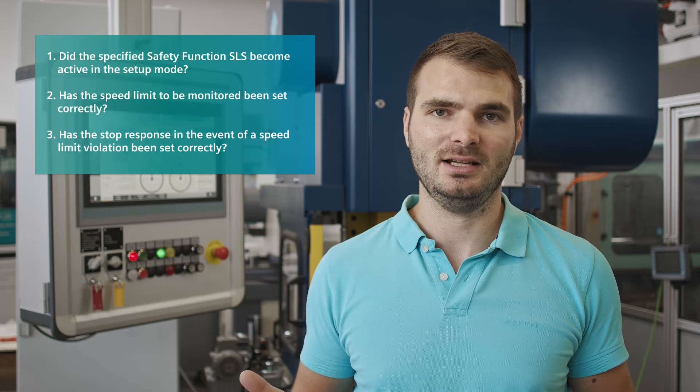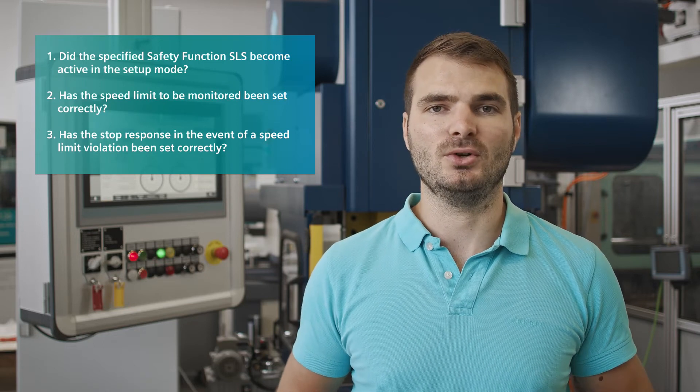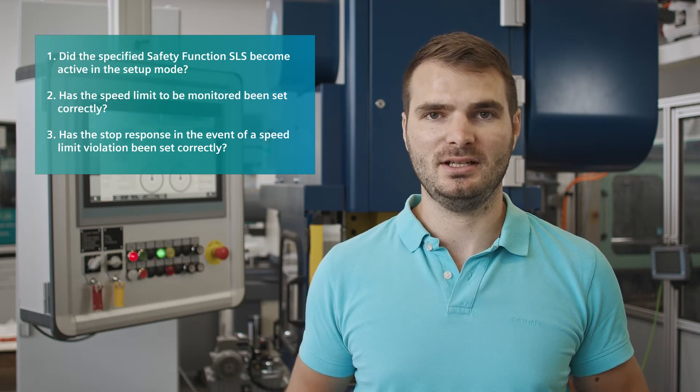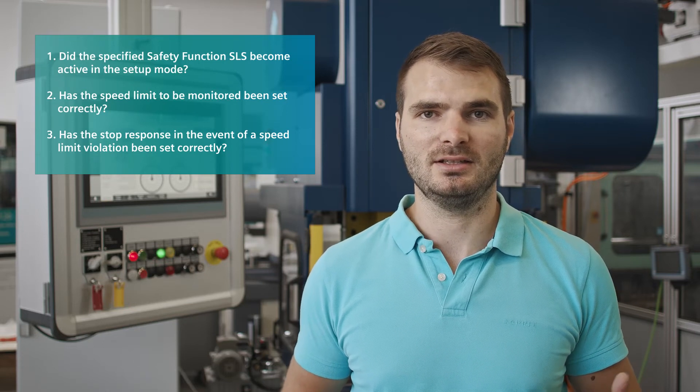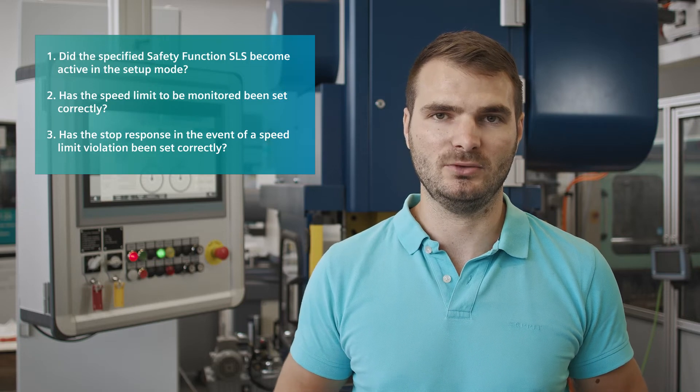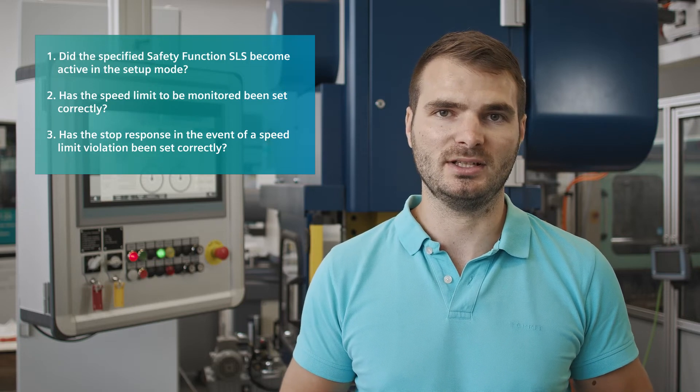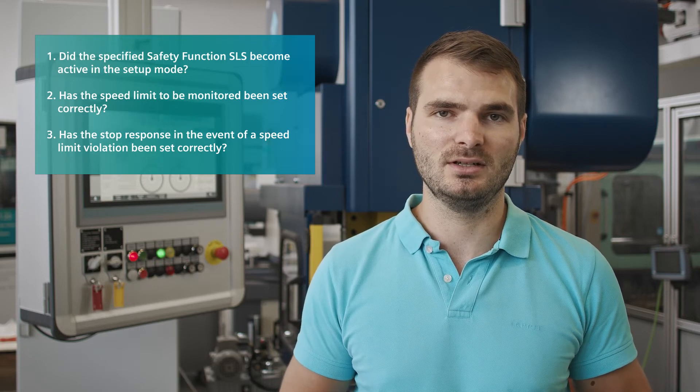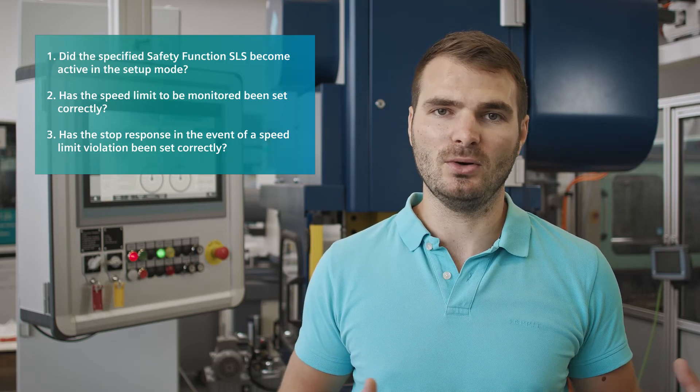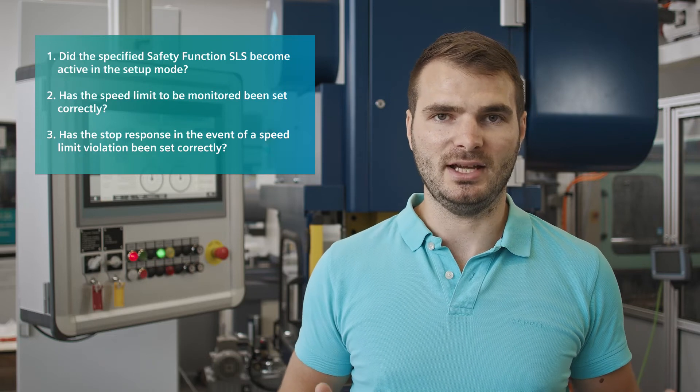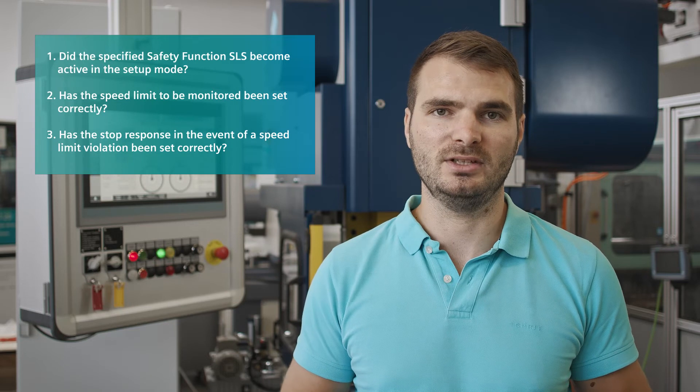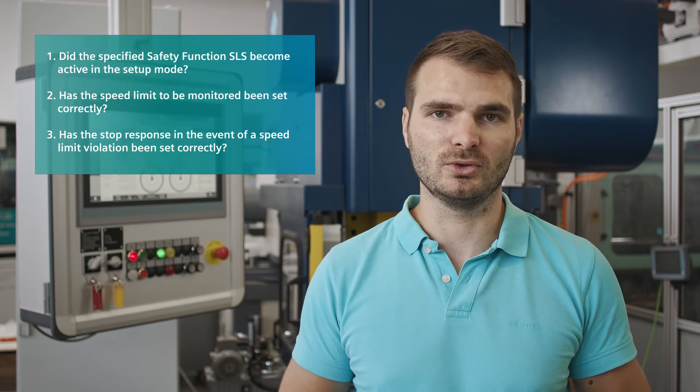Again, we cannot see whether SLS has actually become active, nor can we see whether the speed limit of 20 strokes per minute has been set correctly or whether SS1 has been configured as a stop response. And this is exactly why we carry out this function test and start the acceptance test in a similar way to the SS1 test.